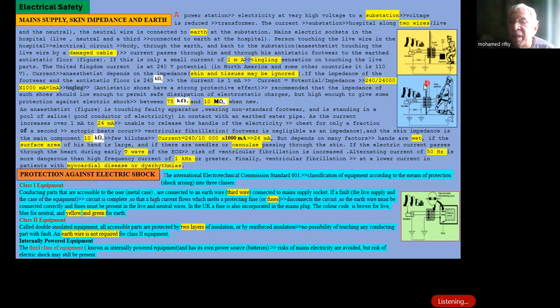This is another figure showing personnel carrying equipment while touching a pipe. This pipe is touching a pool of saline. The saline is a good conductor of electricity, and there is a fault in the earthing wire, so the electricity goes through him, reaching the earth through the pipe, and the circuit is completed, and he can be affected. If this current reaches 24 milliampere, it can induce ventricular fibrillation.